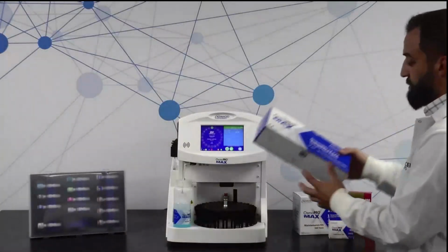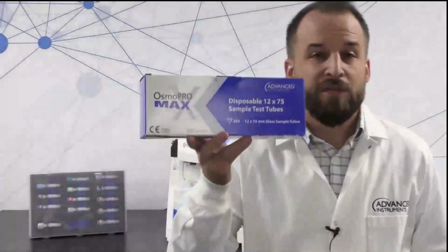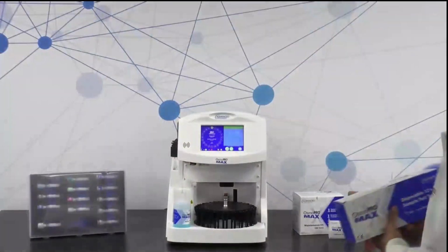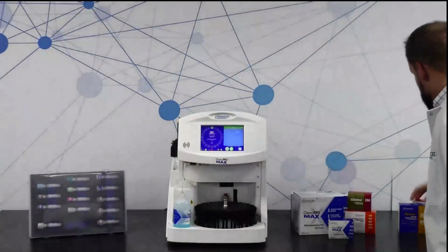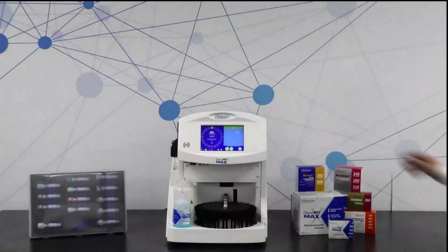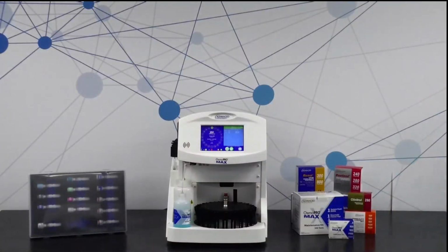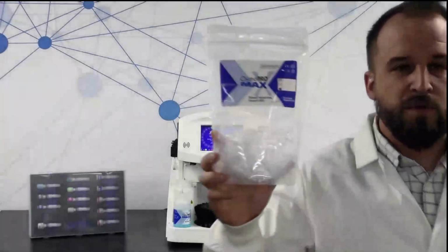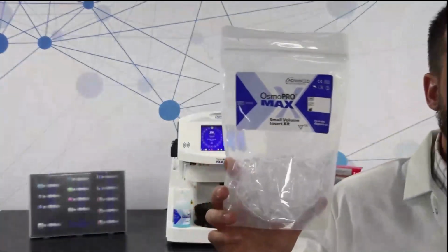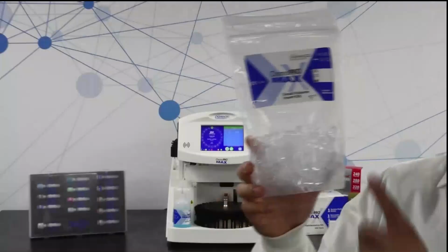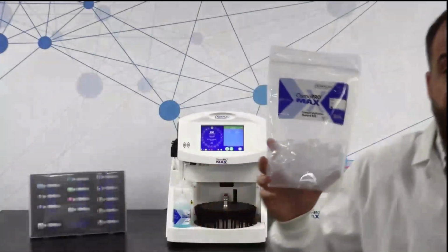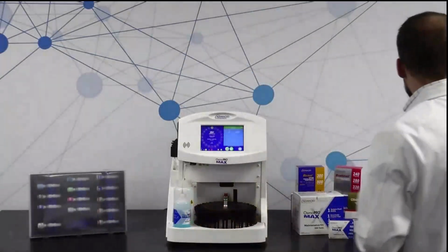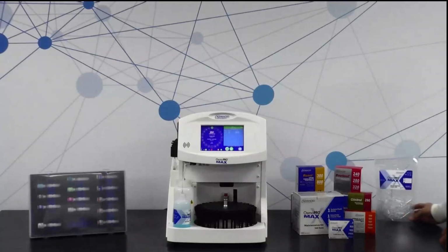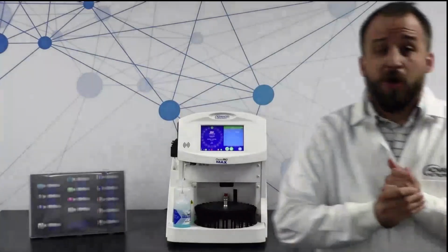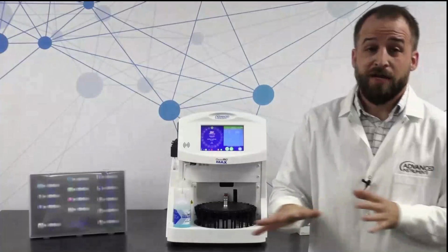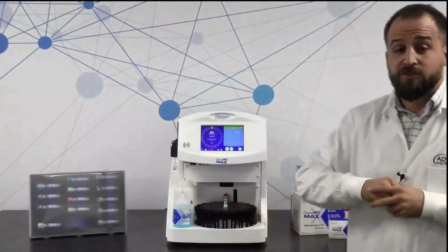Additionally, you can get these tubes. So we do sell these 12 by 75 millimeter tubes, primarily for if you have the need to run a small volume insert, which are also going to come with the starter pack, with the convenience kit that you get with the OsmoPRO MAX instrument. So these small volume inserts are going to be really important for your short draws, maybe pediatric samples. The minimum sample volume that you can run in the small volume inserts is 190 microliters. So 190 microliter minimum sample volume on this instrument.